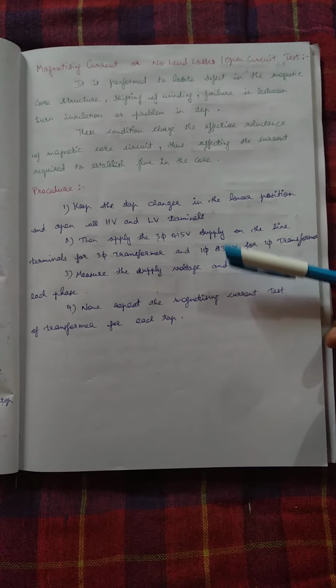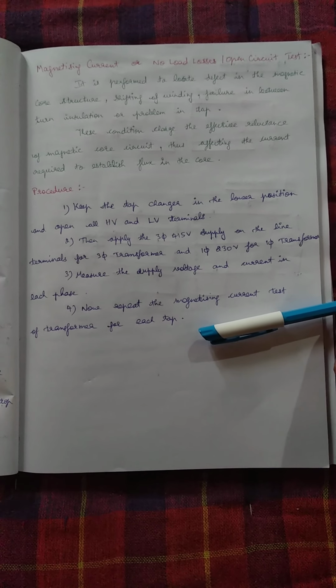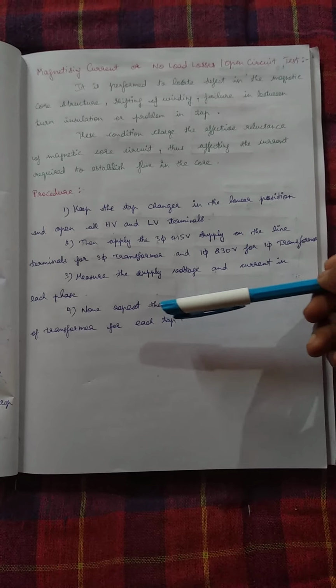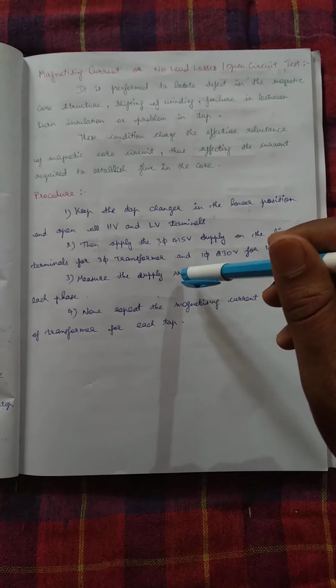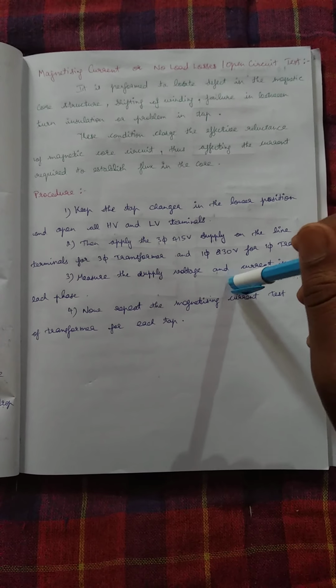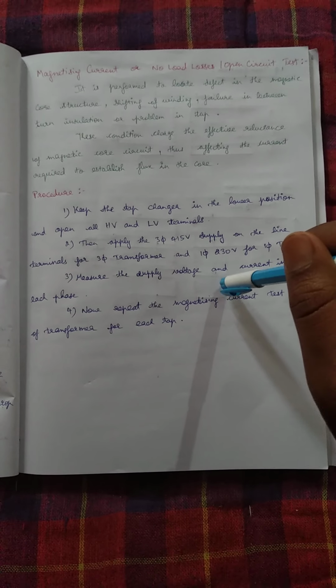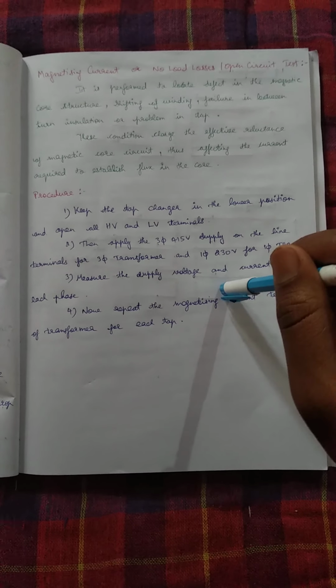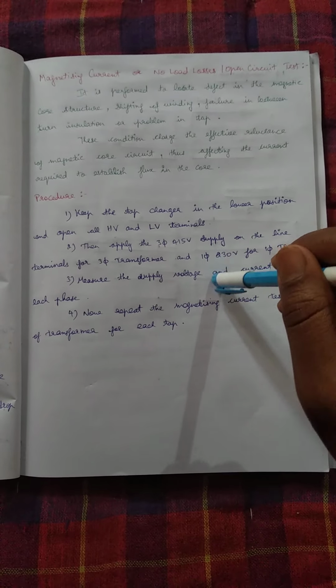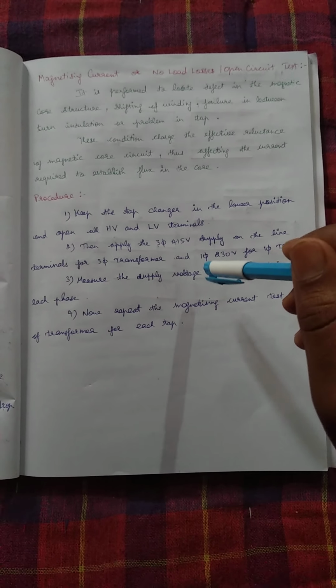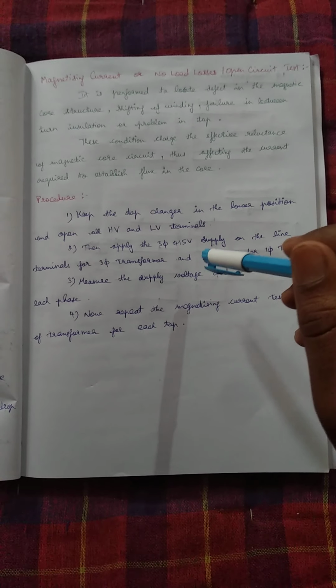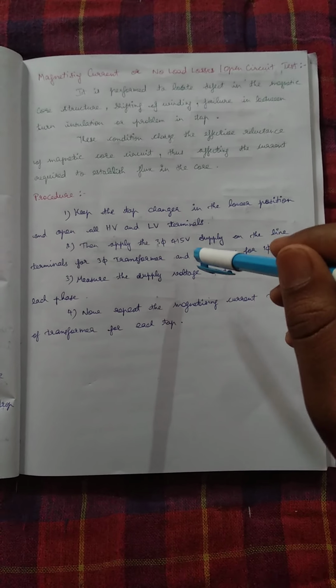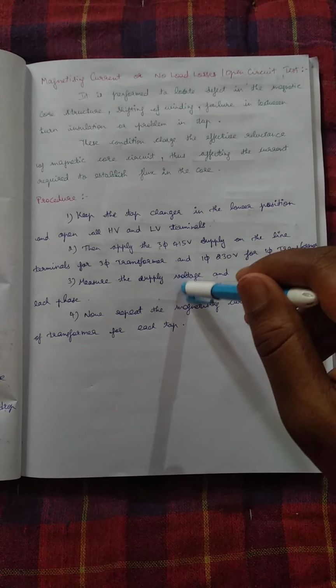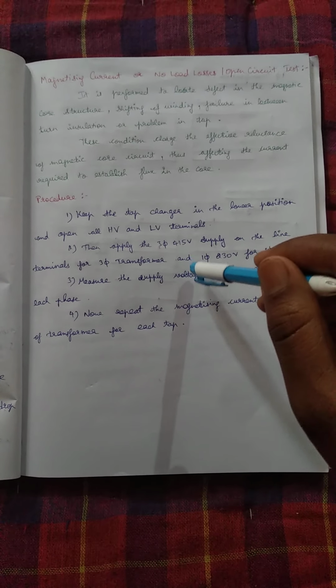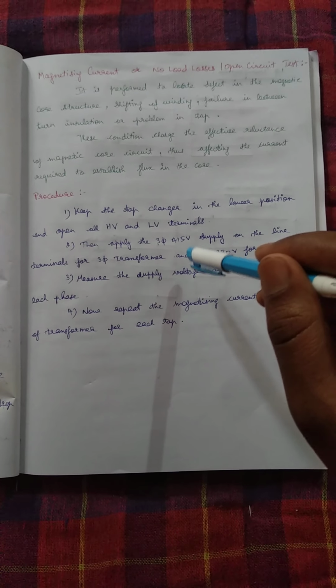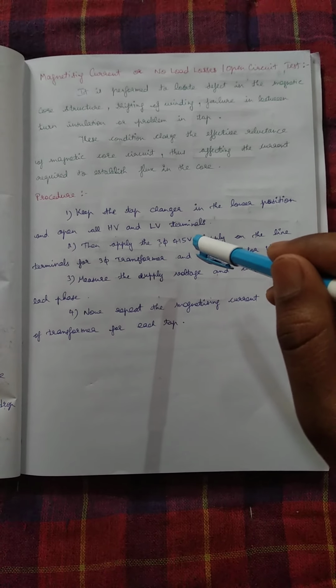It is a very simple test, but it can be dangerous to the transformer and also to humans, so we need to be very cautious during this test, because in this test the secondary side will be open circuited. If anyone unknowingly touches the secondary side or shorts the secondary side, the short circuit current will fall into that person or material. So you should be very cautious during this test.